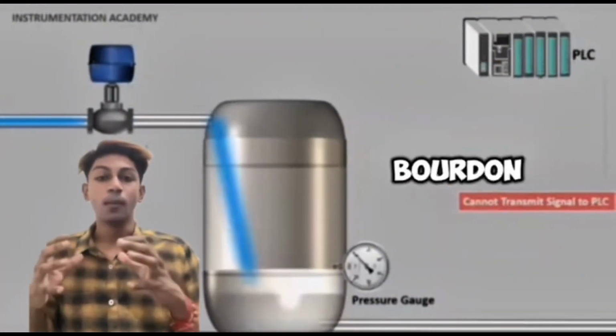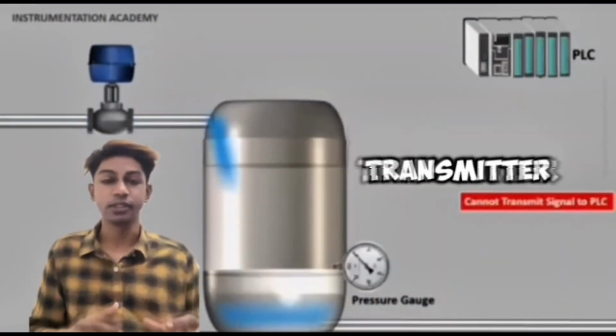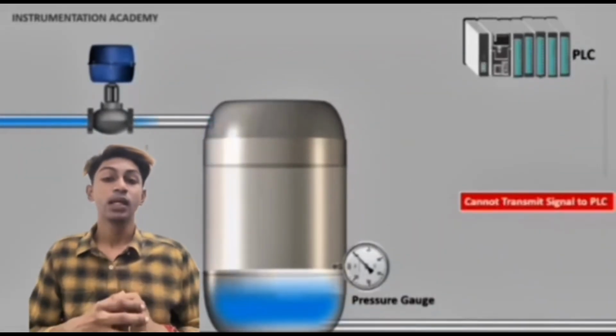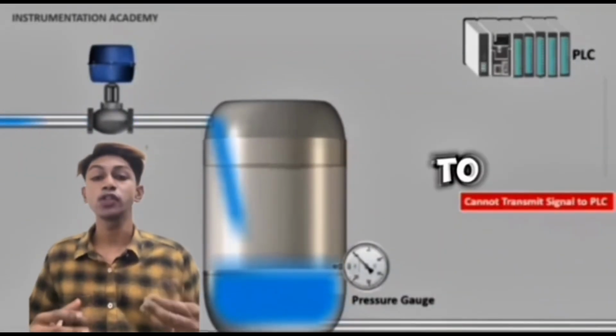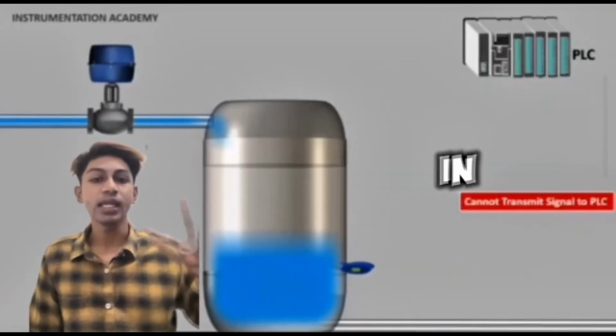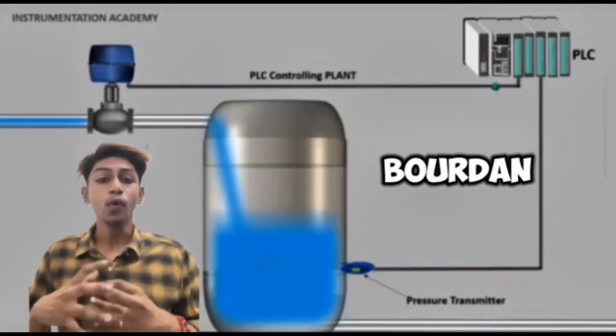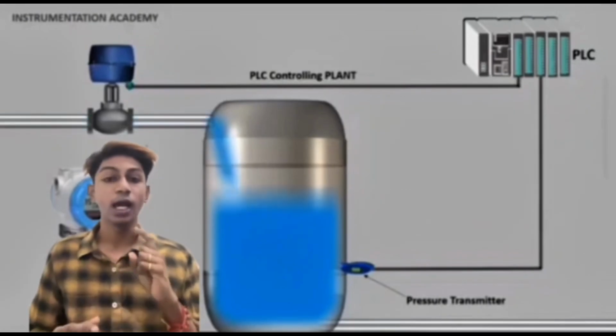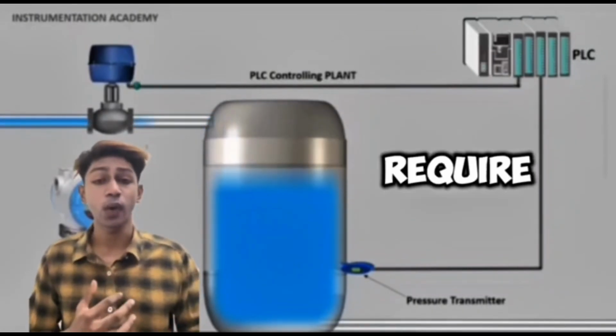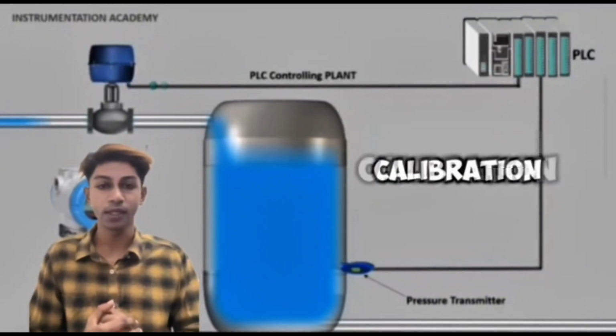Now we are going to talk about the difference between Bourdon tube pressure gauge and smart DP transmitter. First, in terms of cost. Bourdon tube is much cheaper compared to smart DP transmitter. Second, in terms of maintenance. Bourdon tube doesn't require high maintenance. Unfortunately, smart DP transmitter requires high maintenance and periodic calibration.